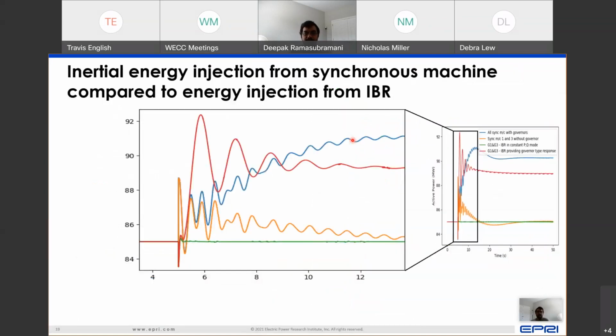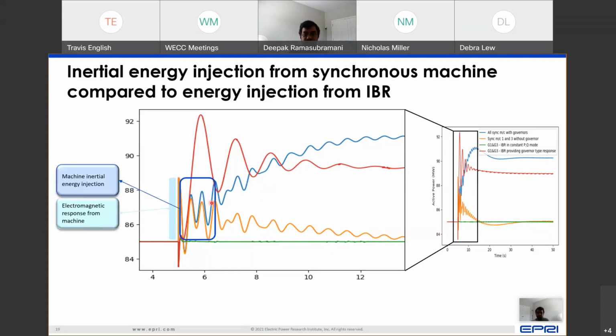Because if you look at the frequency response behavior in the small time frame as soon as the disturbance occurs, and if we compare having all synchronous machines with governors as the blue curve, synchronous machines with governors turned off, which is the orange curve, and then an inverter-based resource providing governor-type response, as soon as the disturbance occurs, the initial response that you see, the spike, is not to be confused with inertial response from synchronous machines. That spike is a pure electromagnetic response that comes from a machine. The inertial response follows that.